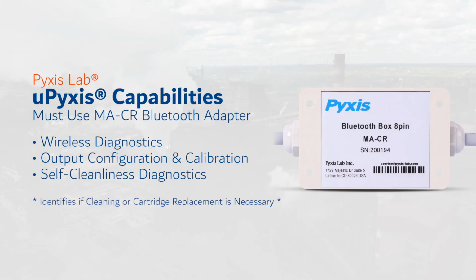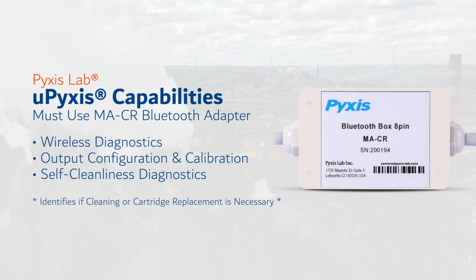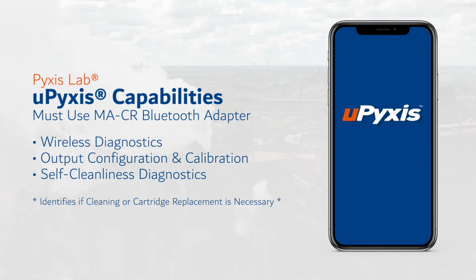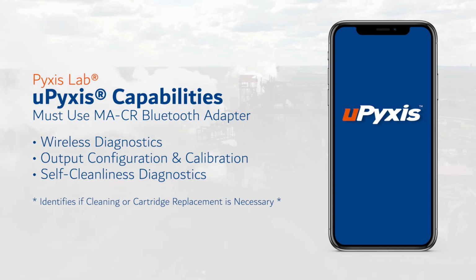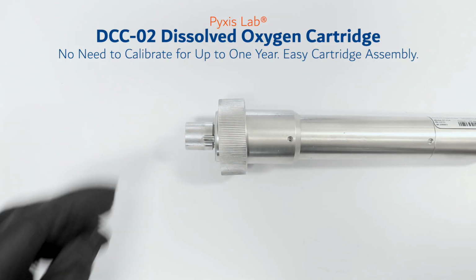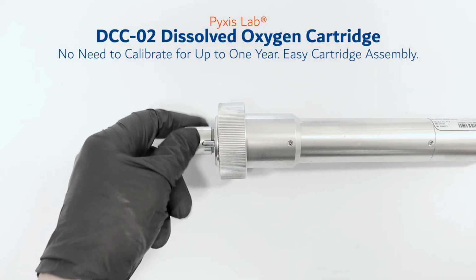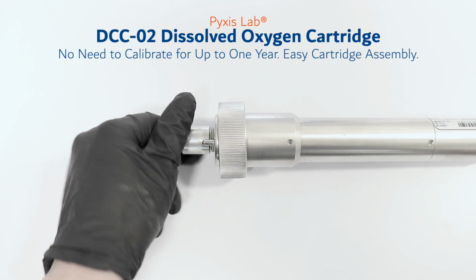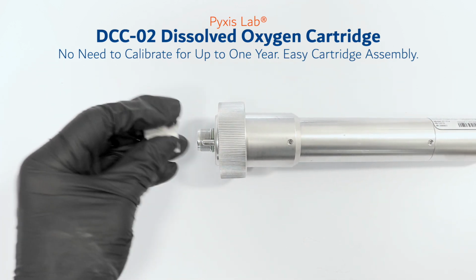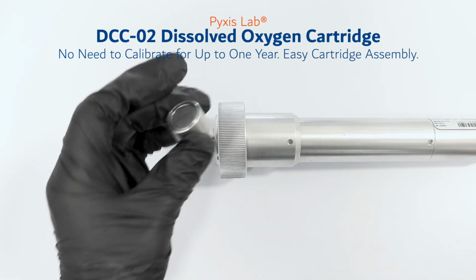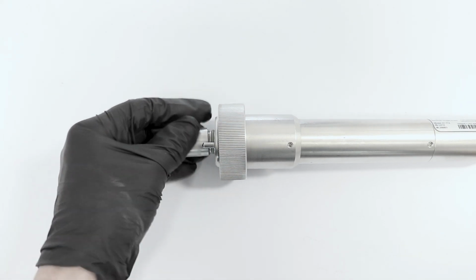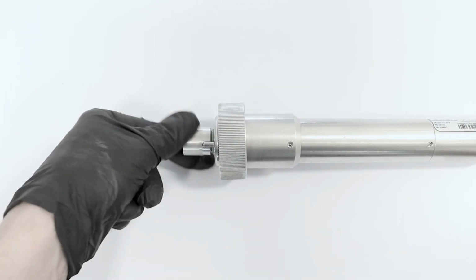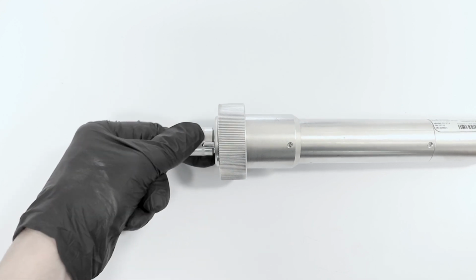The ST-774 is also Bluetooth enabled when used with the MA-CR Bluetooth adapter for convenient and wireless diagnostics, probe output configuration, and calibration via the Pyxis mobile or desktop app. The ST-774 offers a cleanliness self-diagnostics capability within the Pyxis app as an added convenience to determine if the sensor requires cleaning or cartridge replacement. The ST-774 can be deployed without the need for calibration for up to 1 year of operation. Maintenance of the ST-774 is quick and easy, with interchangeable DCC02 dissolved oxygen cartridge assembly. To remove the old cartridge, simply twist off the expired DCC02 cartridge, replacing it with a new one. The ST-774 dissolved oxygen sensor is now ready for service.